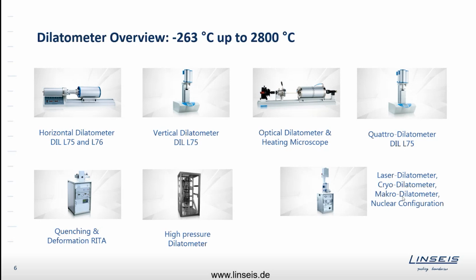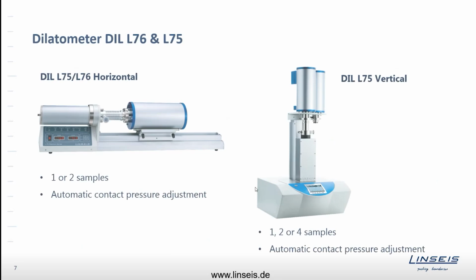We have macrodilatometers for very big samples, and we have a special configuration for nuclear samples where you separate the electronics from the furnace more or less to be able to run under very corrosive, very toxic, and irradiating atmospheres. So that's the complete range that we offer. As I promised, I will just go into detail and explain a little bit the differences and advantages and disadvantages between the different versions. Starting with our standard configuration, horizontal and vertical setup.